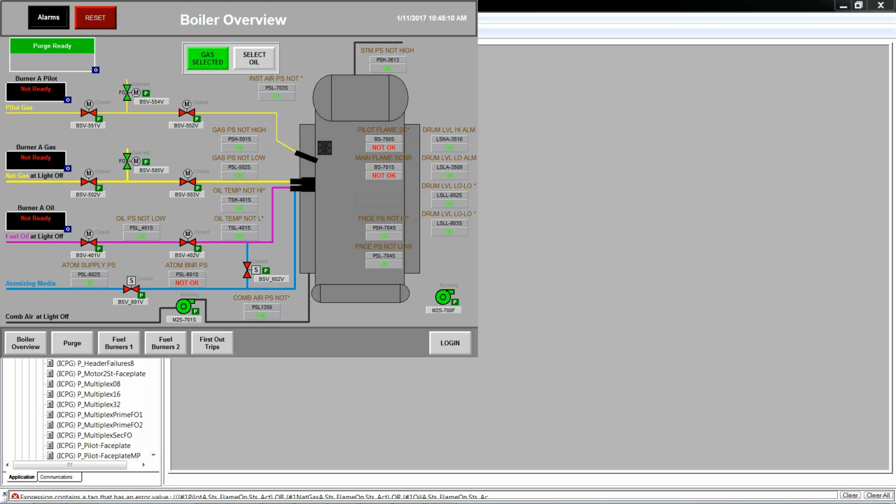And this safety PLC is basically one side has memory, processing and I/O for the safety side of things, and one side has its own memory, I/O and processor for the process side of things. And what we're looking at is taking our current solution or interpretation of two PLCs, one for process, one for safety, and putting them both into a GuardLogix processor.